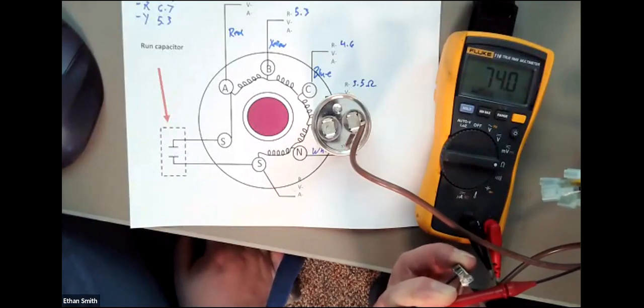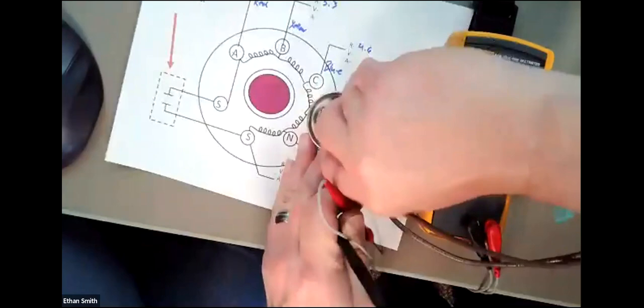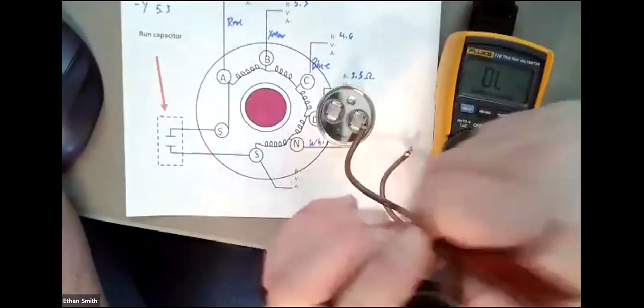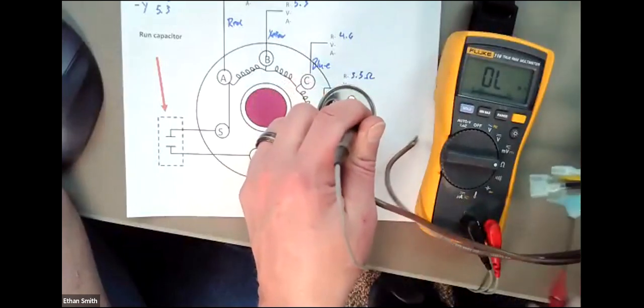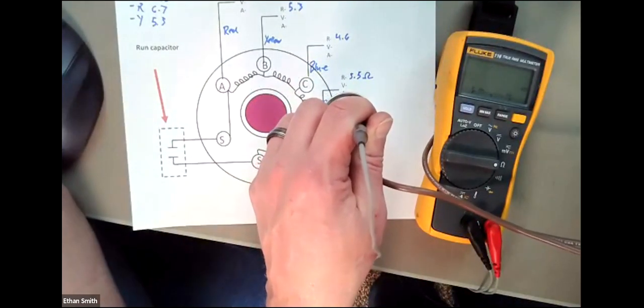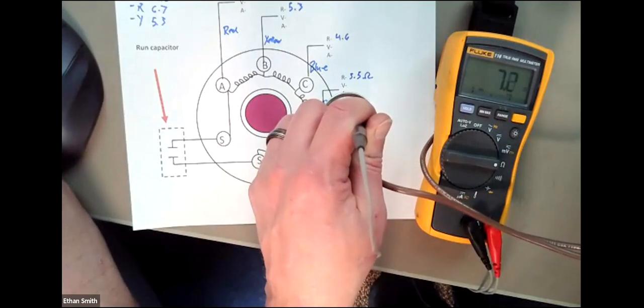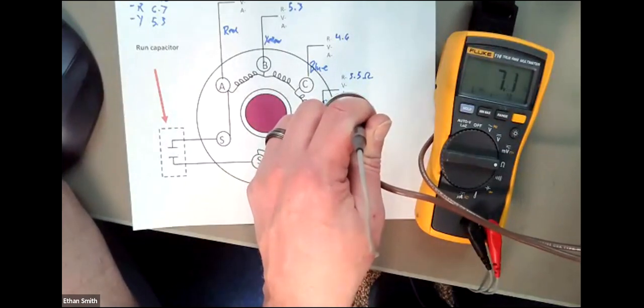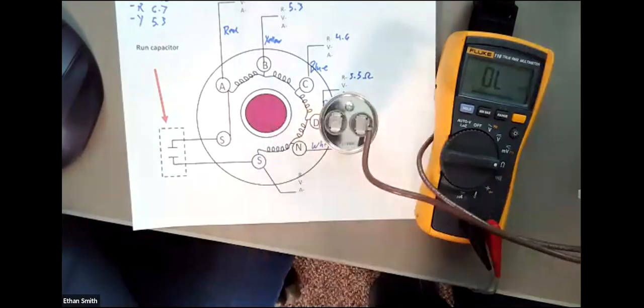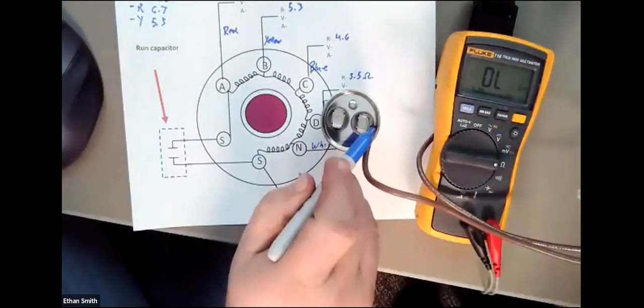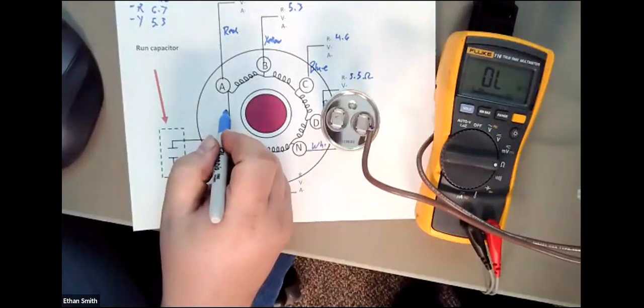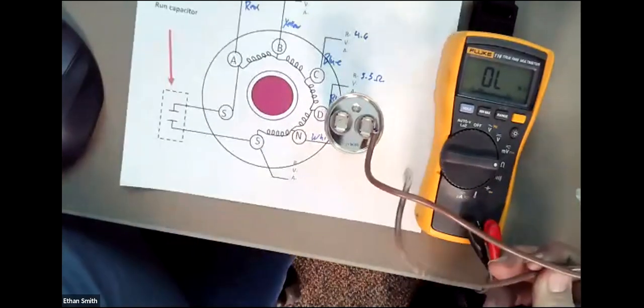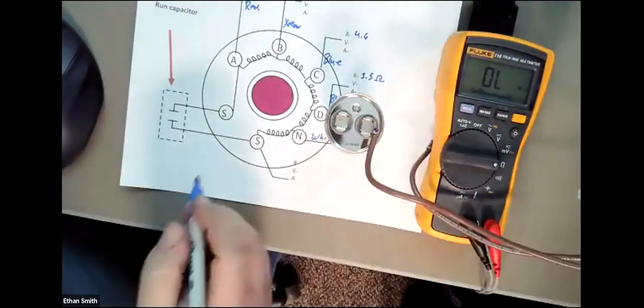74. 74 ohms. Okay. Want to check the other one? Yeah, check it to the other side. It's isolated already. And so you can actually tell which side of the capacitor is which when you do this. So that one's 7. So we can tell that this wire right here is this one. Do we have any identifiers on these, or are they just both brown? Yeah, they're just both brown.